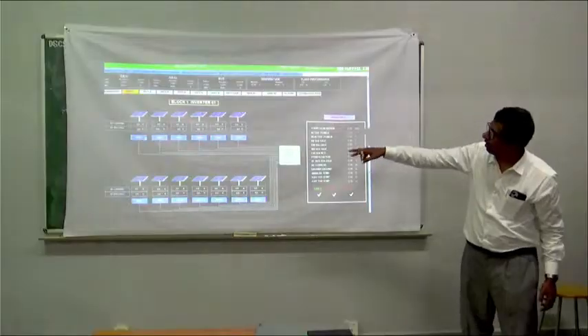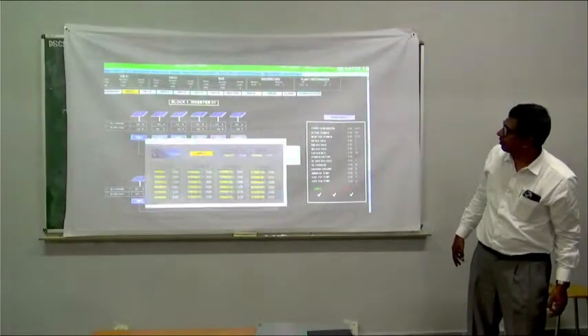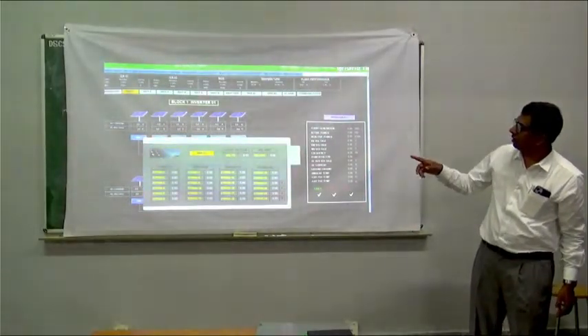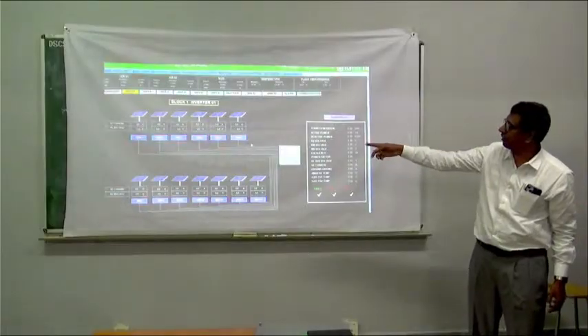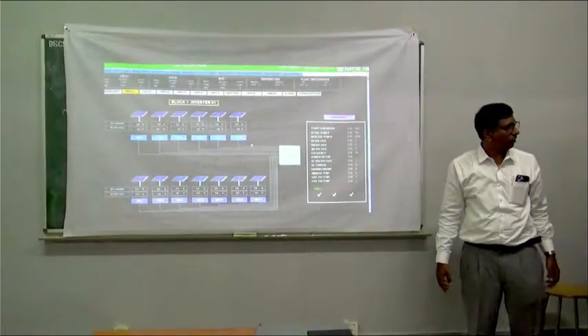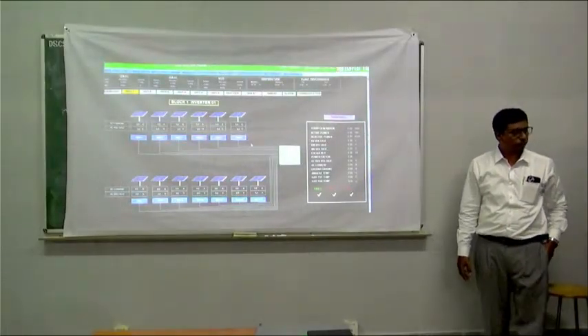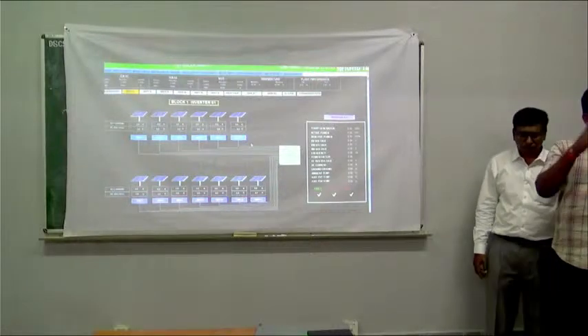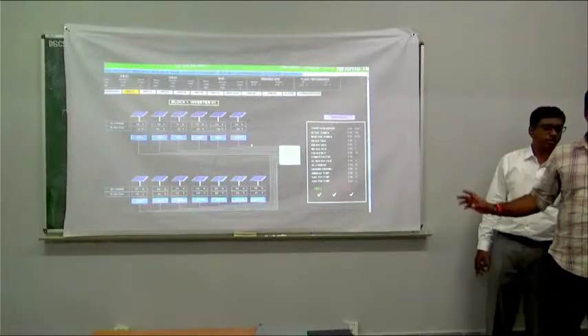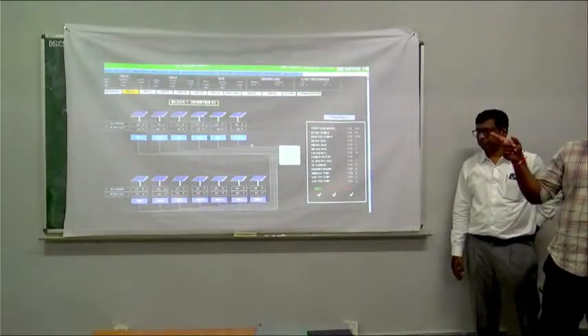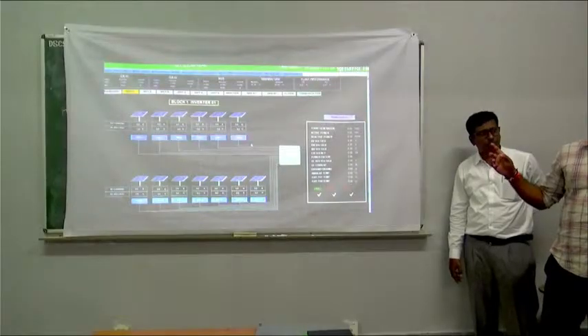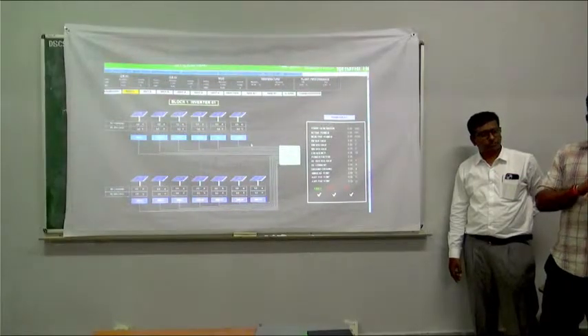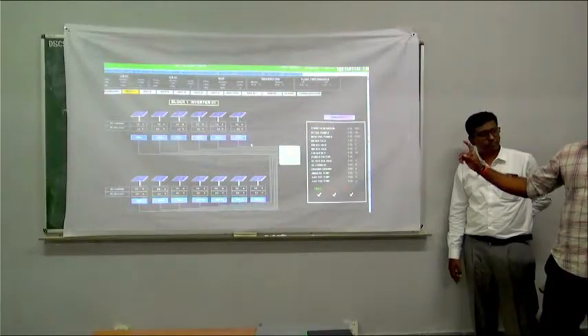Those strings will finally be connected. Now if you come closer, one inverter will have so many string monitor boxes. If you come to the inverter, it's a collection of all the SMBs - all string monitoring boxes - connected in parallel only, because they need to maintain the same voltage. That's why they maintain parallel connection.